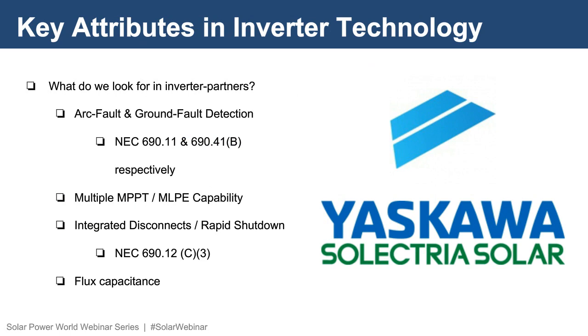Inverters are at the heart of every PV system. As such, there are many features to look for when specifying these units to help you achieve safe, code-compliant PV systems. CivicSolar looks for these distinguishing features in string inverter options: arc fault protection, interruption, ground fault detection, multiple MPPT or module level power electronics capability, integrated disconnects, rapid shutdown capability, and easy to deploy monitoring solutions. The Yaskawa Solectria equipment are excellent examples of products that include these features.